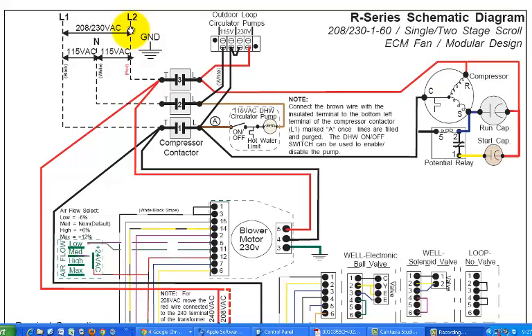Now, having said that, we should back up a little bit and say, this instructional video isn't attempting to teach the safe use of the voltmeter. Do note that we're talking fairly significant voltage, and even more critical from a safety perspective, there's a fair bit of amperage behind these, depending on the size of the heat pump, etc., and ultimately, of course, the size of the breaker that's feeding that, but lots enough amperage to be dangerous.